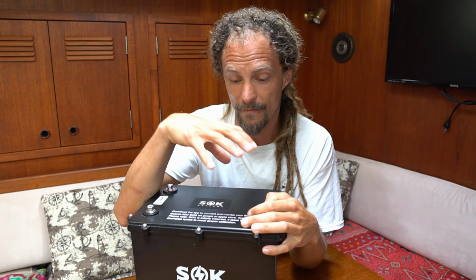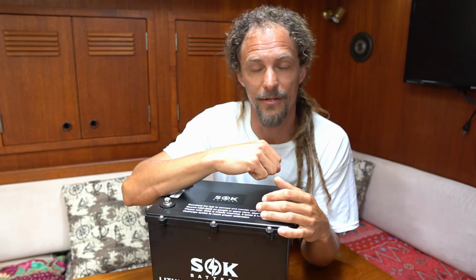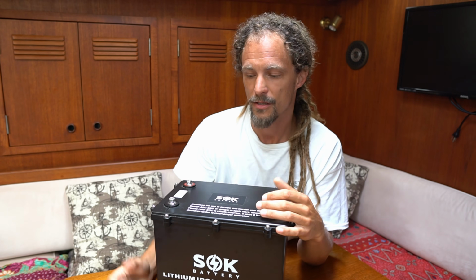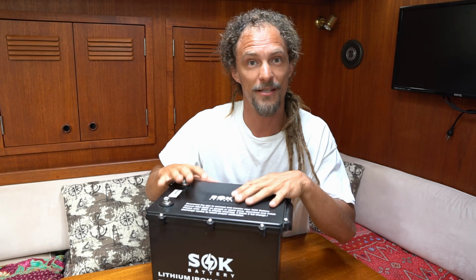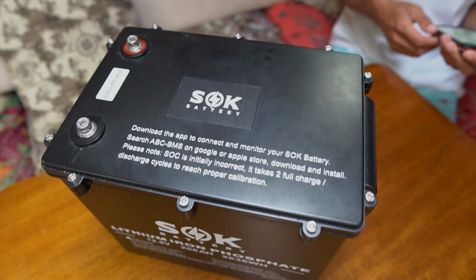Actually, when I fully cycled one of these batteries, it's getting closer to like 230 amps, or 200, getting a little bit more amp hours out of these batteries than what they're rated for, which is what you'd expect. You don't want to get a 200 amp hour battery and it's actually a 180 amp hour battery. So it's good to see that they undersize the rating of what these batteries actually are, and you're actually getting slightly more than what you're paying for.